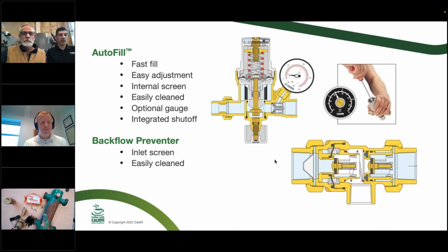So where would you see one of these come back? What's the symptom that you would see as a return? Oh, geez. All right. So just coming from the field myself, and Bob, you can probably relate, the biggest reason why we get these devices back is because the backflow preventer drips on the ground. Is that right, Bob? Yeah, they drip or they spit or they go off. Yeah. And really, in all reality, especially the consistent dripping type ones, it's not a testament of product quality. It's a testament of the water quality that's going through there.